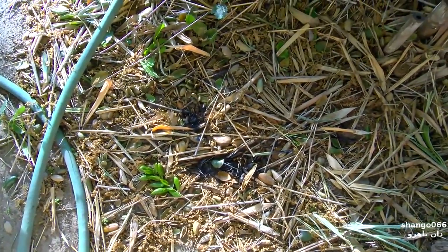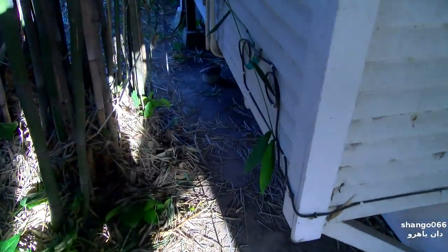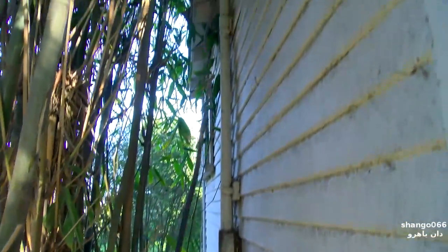This is 10 gauge wire. You can see we had a little fire starting here, and then as it goes out to the street where the pole is, there were several other little fires that I was able to put out with a carbon dioxide extinguisher. This is very crappy — there are several splices in here.